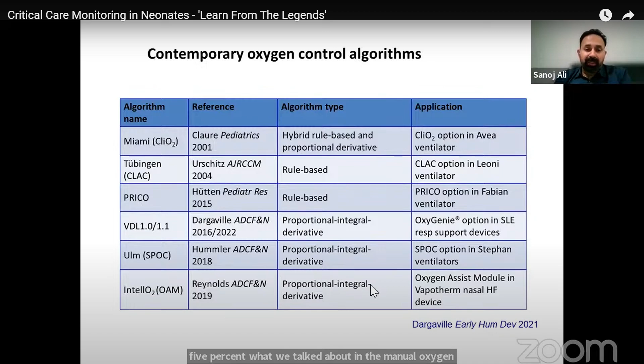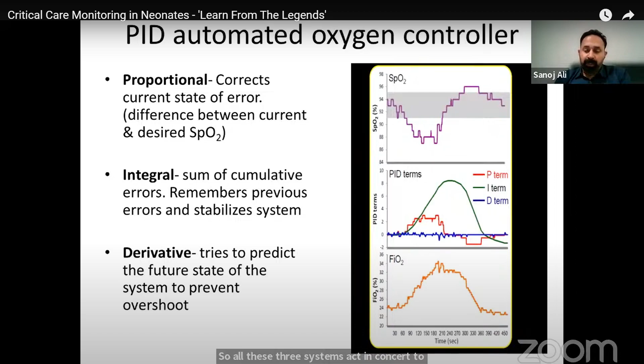But the PID algorithm, which you can see in the OxyGenie and the SPOC, is probably the most effective one. And we'll talk about that a bit more, what PID means. So PID stands for proportional, integral, and derivative. The proportional term is a coefficient which corrects the current state of error. That is, it corrects the difference between the current and desired SpO2. This is in very simplistic terms. The mathematician can go into all the various coefficients, what it looks like. The integral is a sum of cumulative errors, so it remembers the past errors and stabilizes the system. Whereas a derivative tries to predict future errors and tries to prevent overshoot. So all these three systems act in concert to try and keep the baby within the normal SpO2 target range.